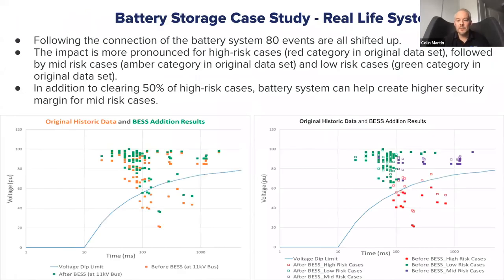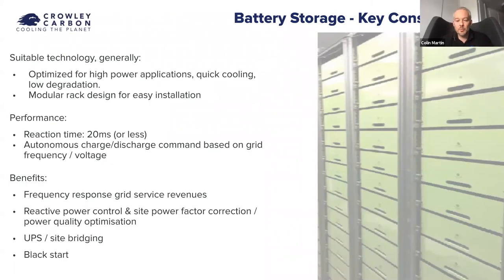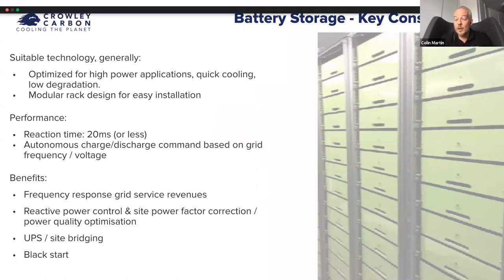The benefits from that, as mentioned, are around frequency response and grid service revenues. There are also a number of power benefits on site: power factor correction, power quality optimization, supporting the site from UPS and bridging. If there's a prolonged grid fault, it allows a calm and measured approach to do some load shedding if the outage looks like it will last longer than an hour, allowing the plant to be shut down in a controlled fashion with critical systems maintained. And if absolutely required, it could support a black start as well, though hopefully that's not a common occurrence.